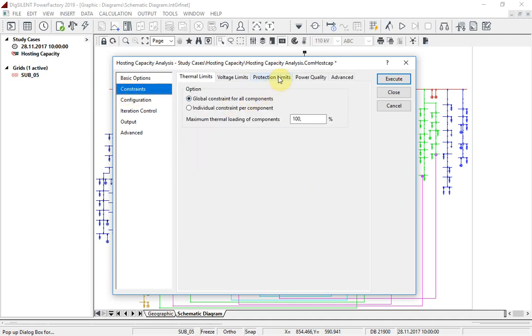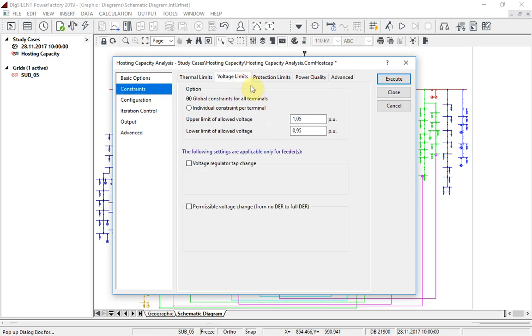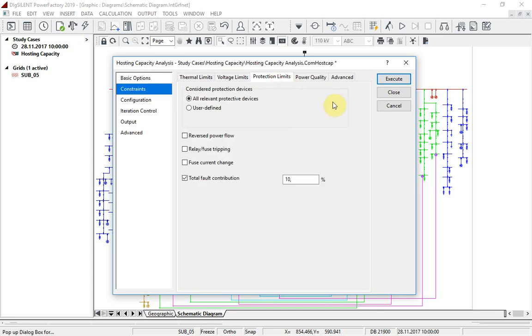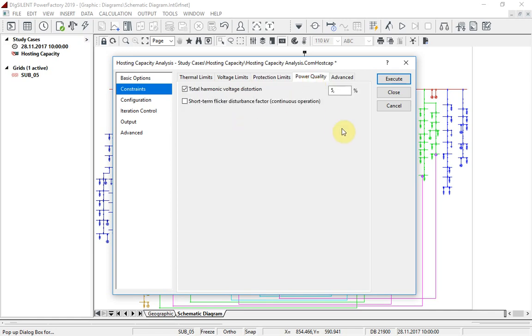On the constraints page, the constraints are configured in detail. For example, when considering protection devices, the user might select to prohibit reverse power flow. And power quality limits are taken into account using harmonic load flow analysis.